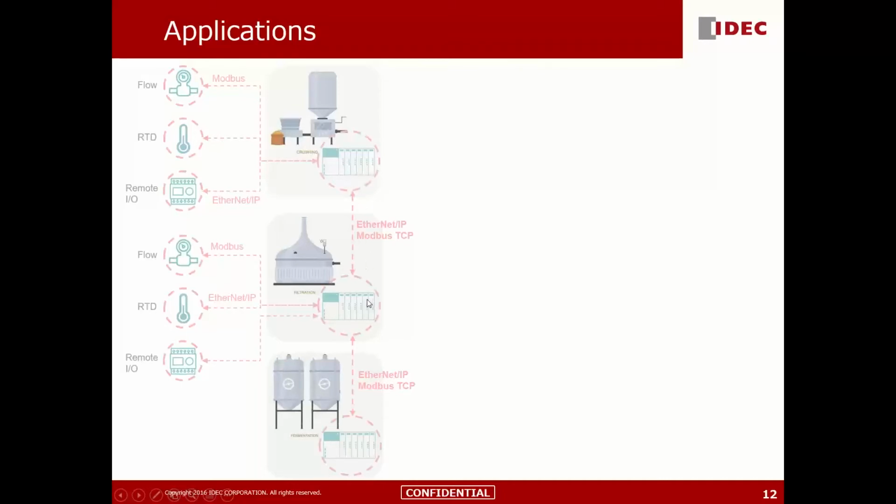nor because each process needs to be able to communicate to each other. Again, most of the time, or the majority of the time, you would use Ethernet IP or Modbus TCP to communicate between devices at this level. Even though MQTT allows you to do device-to-device communication, I don't anticipate this will be the case. We're still going to be using Ethernet IP and Modbus TCP for this instead of MQTT.